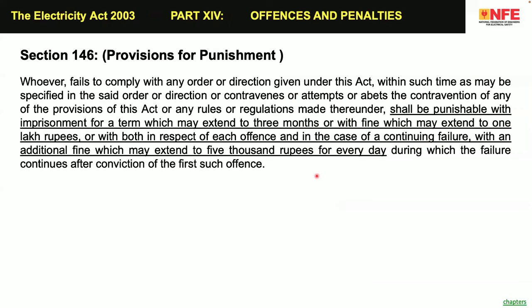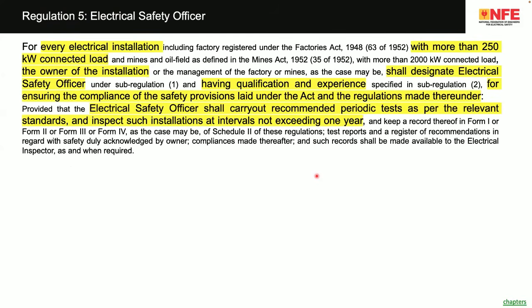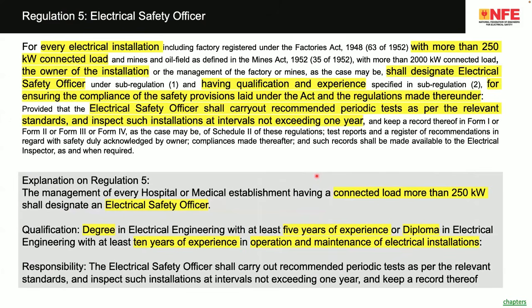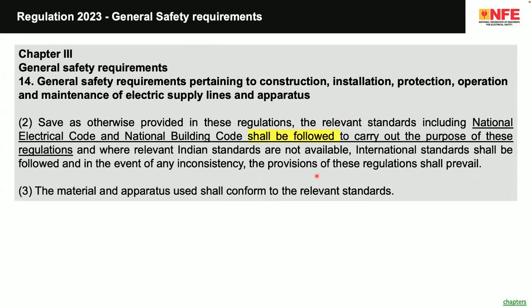That means the hospital owner, the hospital general manager, can be put in jail if the electrical accident is due to non-compliance. Why I made this statement is that almost 98% of the electrical installations in hospitals are non-compliant. So it is very easy. There is a provision for punishment. For every hospital above 250 kilowatt, the regulation says there should be an electrical safety officer who is qualified to handle the subject. This is regulation 5. Regulation 14 says that save as otherwise provided in these regulations, the relevant standards including the National Electrical Code and National Building Code shall be followed. That means you must follow the National Electrical Code and National Building Code to make the installation compliant. The material and apparatus shall conform to the relevant standard.